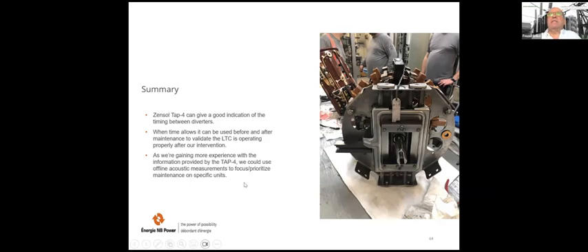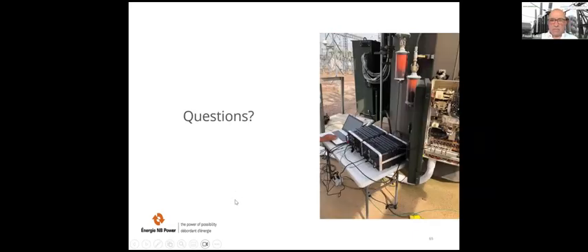So in fact, the idea around this is, if you have, for example, a limited time for the maintenance in summer, you do a quick vibroacoustic test on all your transformers with tap changers. If you have, for example, 10, then you choose which of these 10 transformers you are going to go into deeply. It's what we call to focus and prioritize the maintenance on specific units. So thanks to this quick tool, you can decide which transformer would receive a deep maintenance.